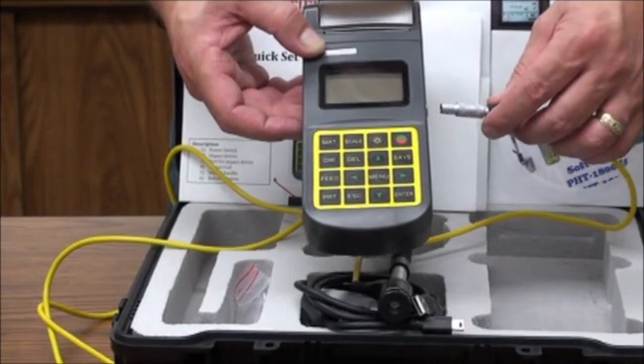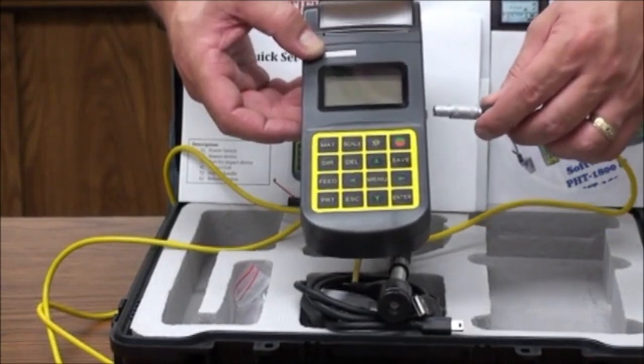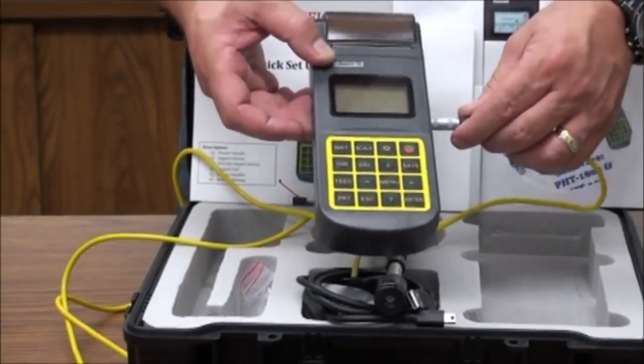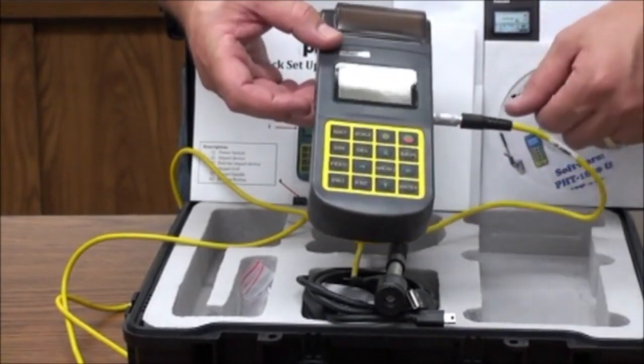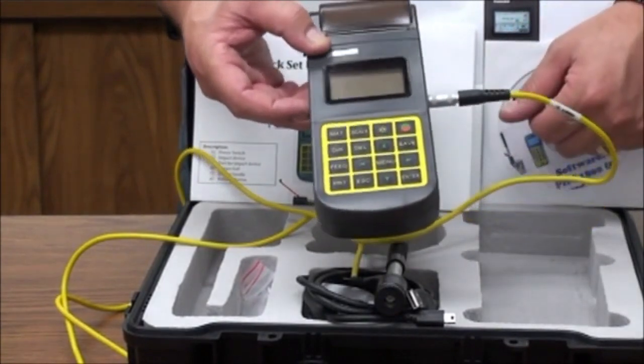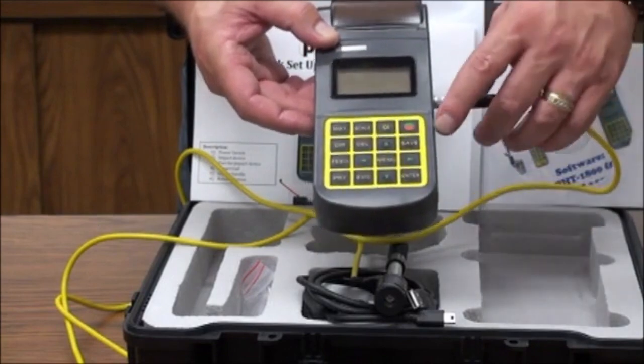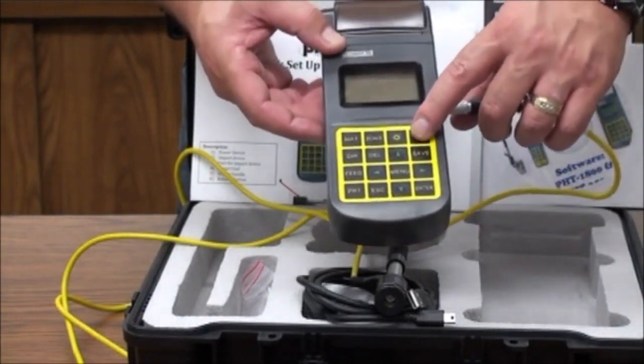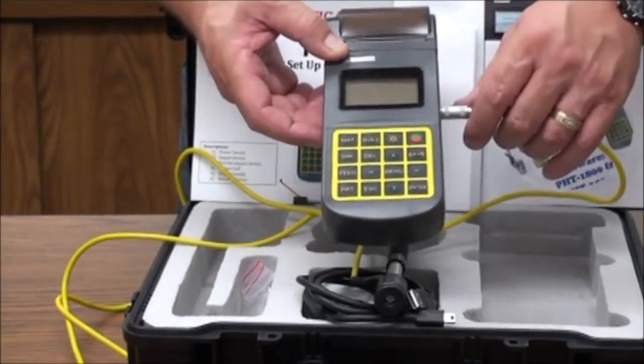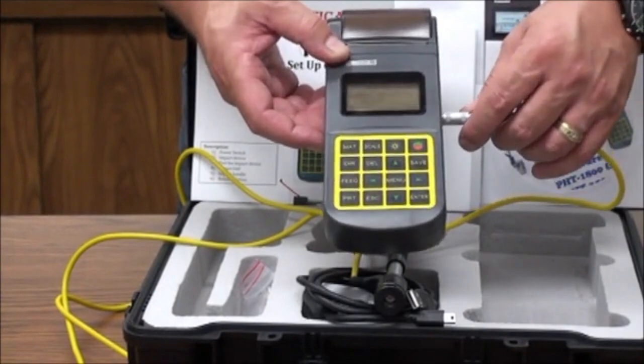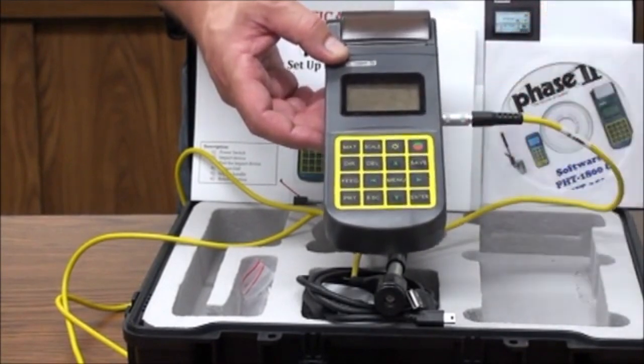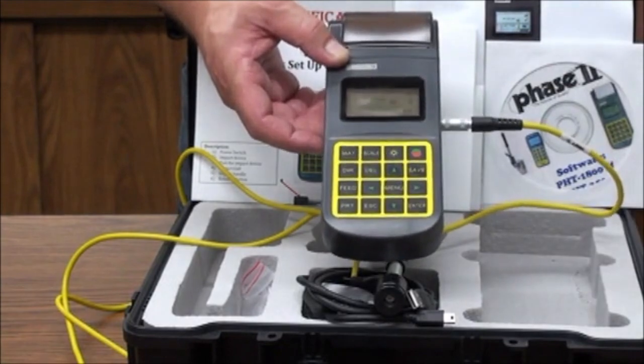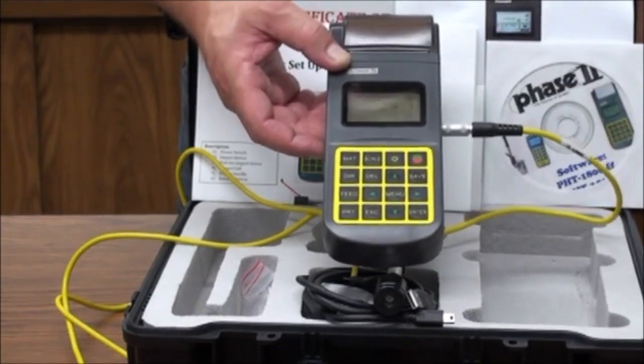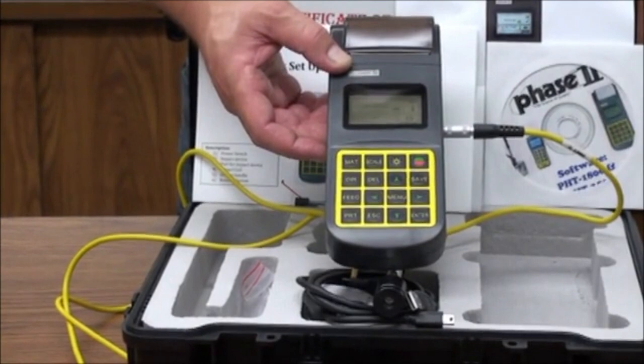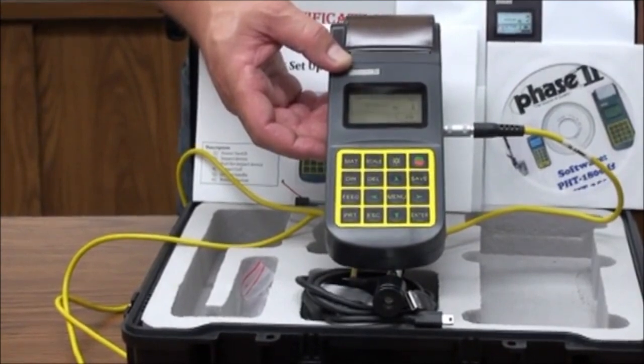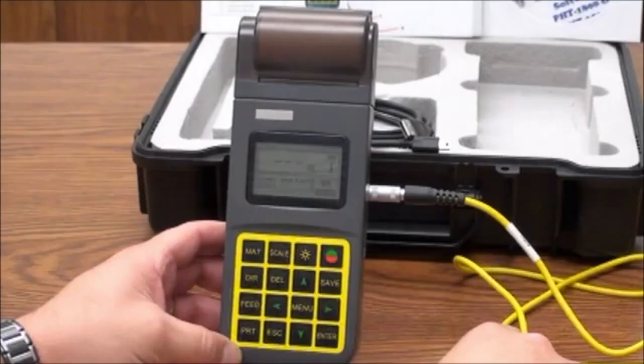To begin, insert the plug of the impact device into the correct socket on the tester. On the left side of the unit, power on the battery switch. Then on the keypad, hit the power button to bring up your test screen. The main interface screen should be displayed. Each indicator on the screen has a purpose. We will go over in detail the meaning of each and how to make any changes if necessary.